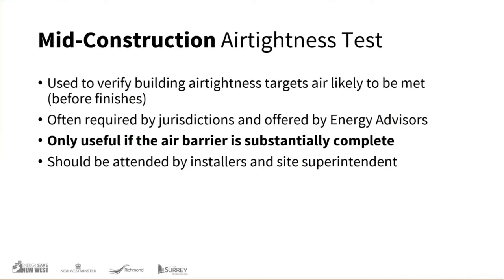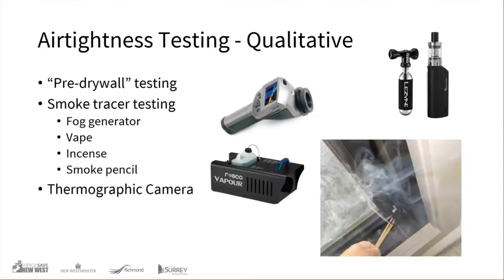On air tightness testing: this generally isn't something the builder or designer undertakes. The energy advisor or energy modeler is the one handling this side of testing, simply using a fan to measure airflow in and out to get your ACH. Before the final test, we have the ability to do a mid-construction air tightness test. It's mandated or incentivized in some cities to get first few buildings tested mid-construction. It's only useful when basically complete — windows and doors in, lockup, exterior sheathing membrane installed, or before drywall if using an interior approach.